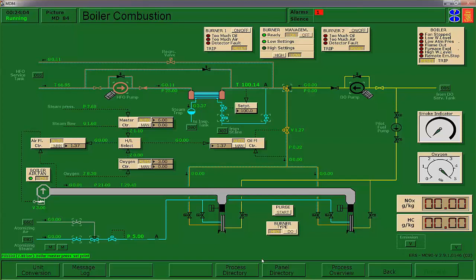You notice that the boiler has cycled off. I also like to go to boiler combustion and decrease the set point on the master controller to 6 bar to help prevent it accidentally starting up. We don't want it running at this point. We want it strictly off the waste heat.